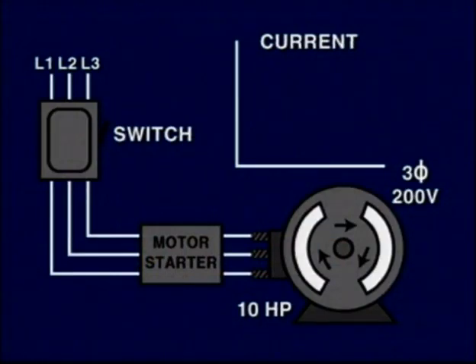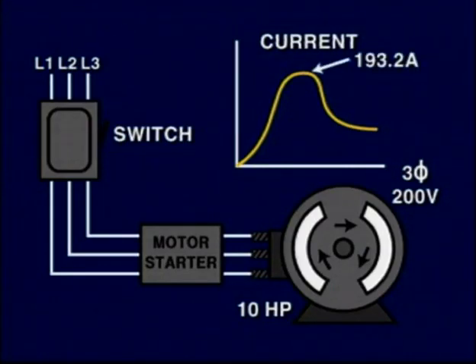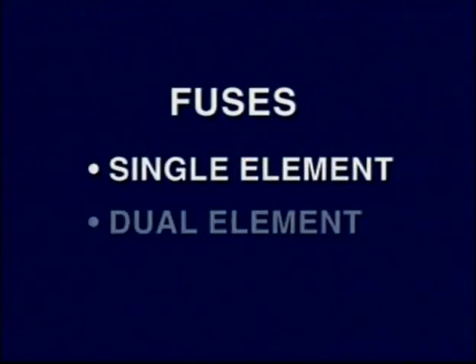Inductive loads, such as squirrel cage motors, will pull between 6 to 10 times the amount of full-load normal current when they are first started. For example, a 200-volt 10-horsepower motor will pull 193.2 amps for a short duration before it reaches its full load amperage current. In this case, it pulls 6 times its full load current. When this circuit is protected with fuses against short circuits and ground faults, the fuse must be able to allow this overcurrent situation without breaking or disconnecting power to the motor circuit. There are single-element and dual-element fuses, each one used in particular applications.